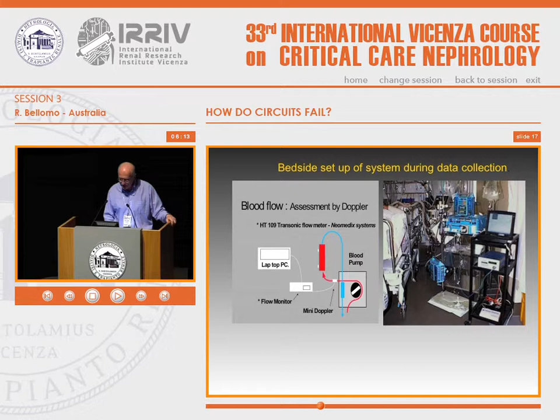And so Ian nicely, some time ago, put the system to a test with a flow probe around the tubing, and we were able to graphically display what might be happening under circumstances of suboptimal catheter function, which are then reflected in some of the pressure characteristics of the pump. And you can see that I scribbled in there is a patient having a nurse change position in this patient, and you can see that there is quite a dip in the negative pressure that is being applied to the circuit.